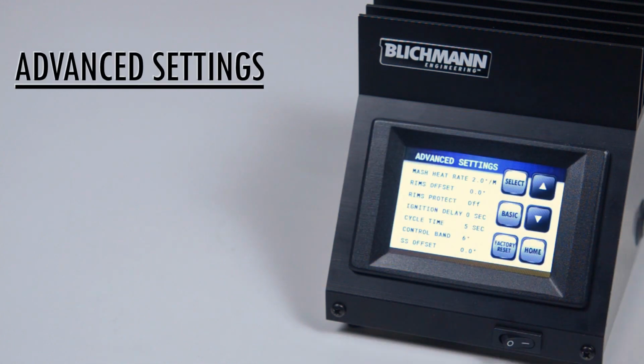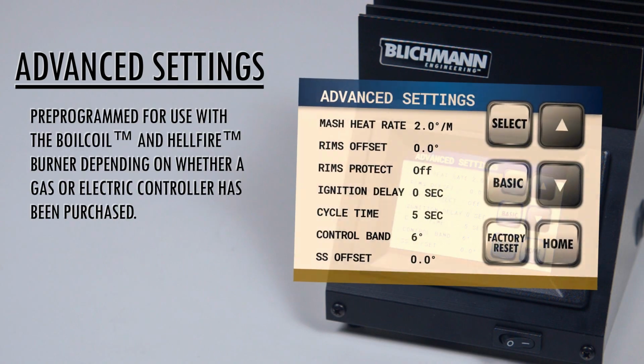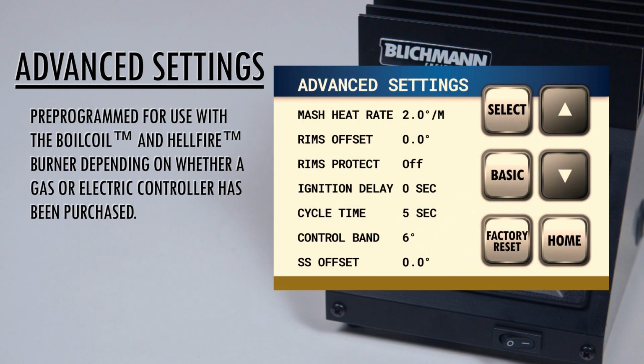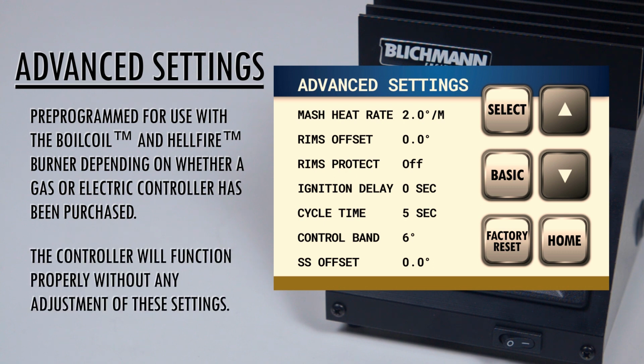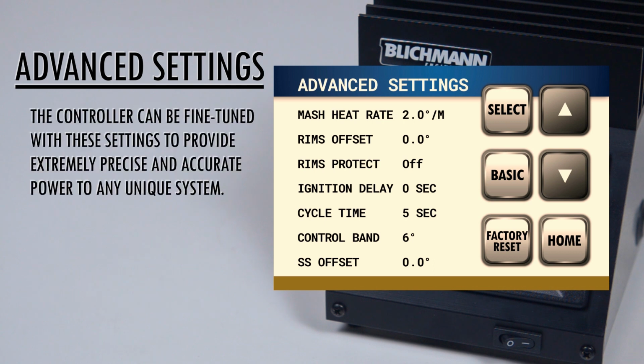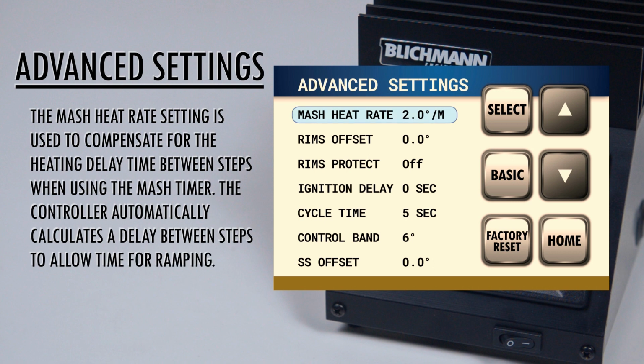The advanced settings come pre-programmed for use with the Blichmann BoilCoil and Blichmann Hellfire burners, depending on whether a gas or electric controller has been purchased. The controller will function properly without any adjustments of these settings. However, the controller can be fine-tuned with these settings to provide extremely precise and accurate power to any unique system. The mash heat rate setting is used to compensate for the heating delay times between steps. The controller automatically calculates a delay between steps to allow time for ramping from the setting.